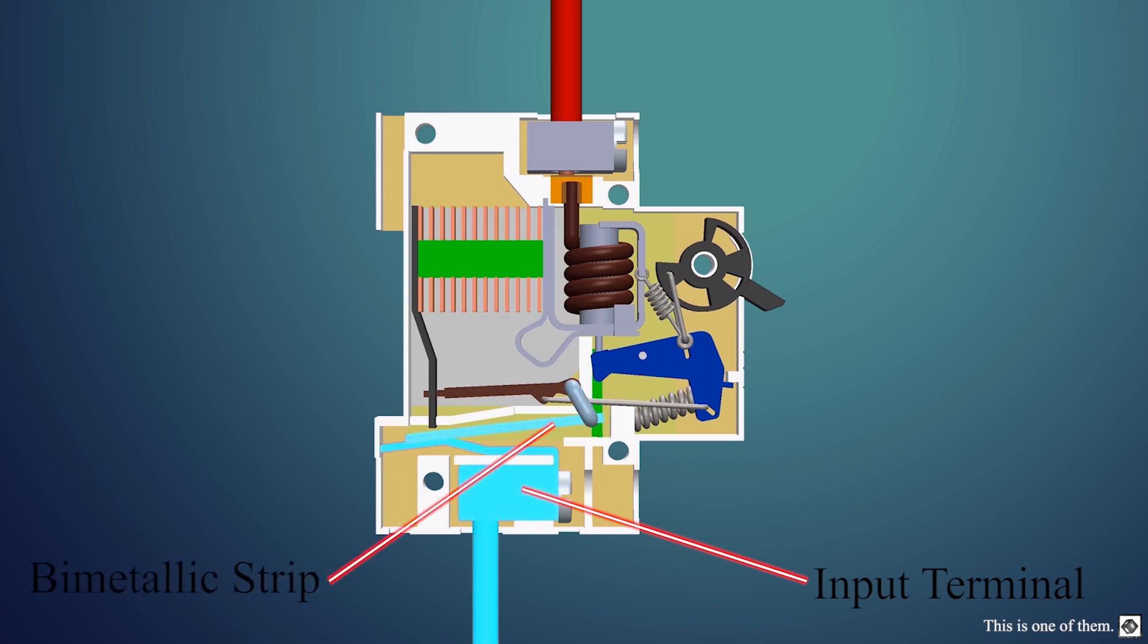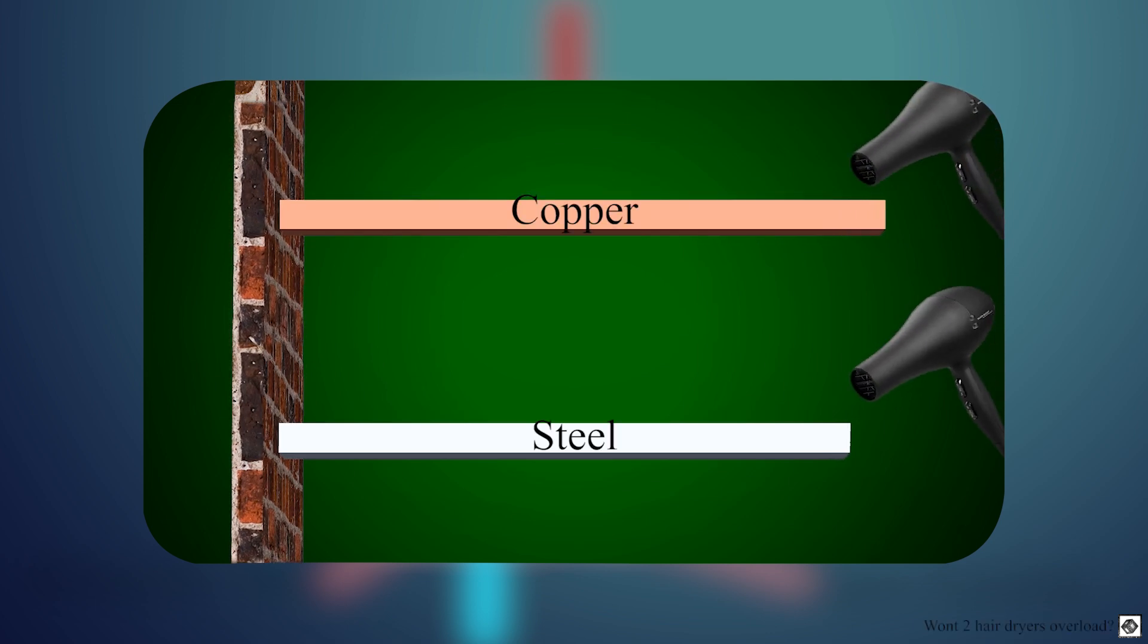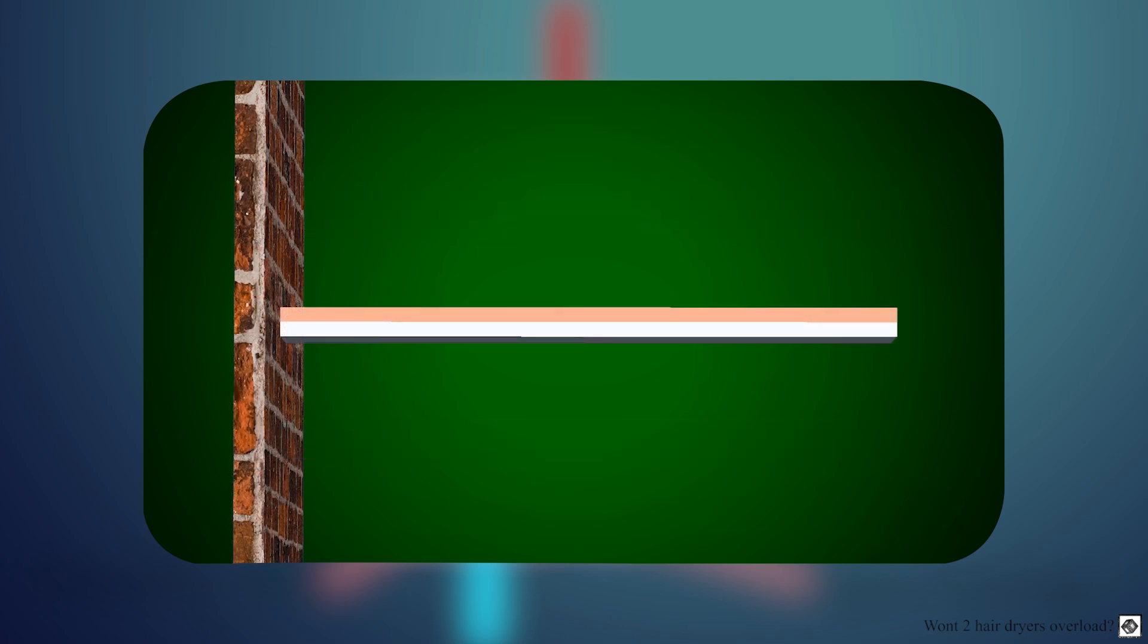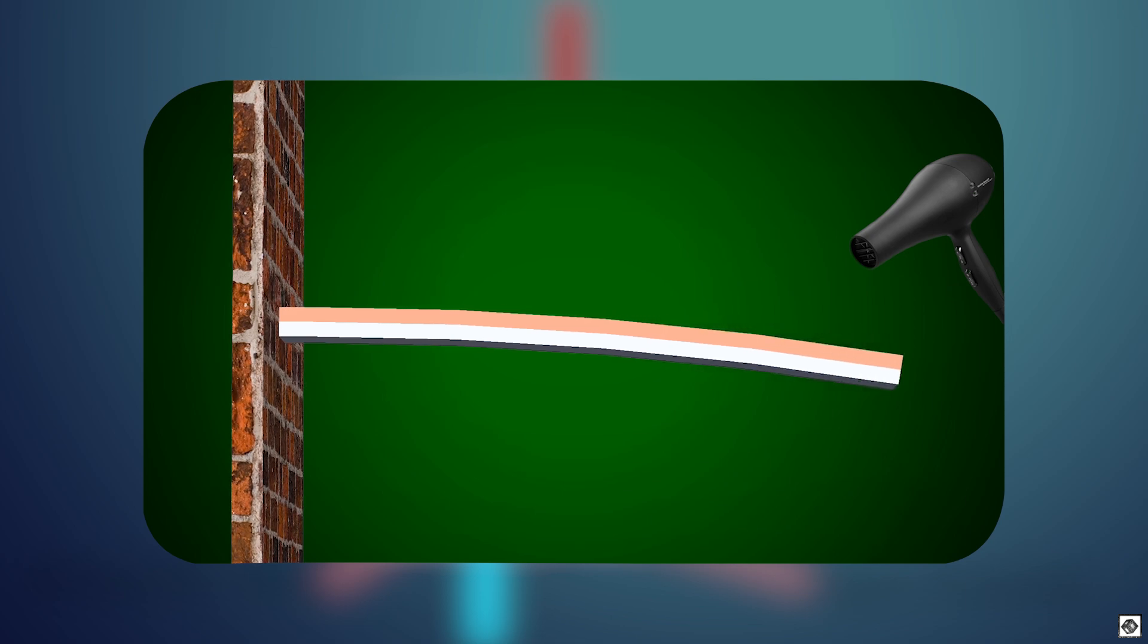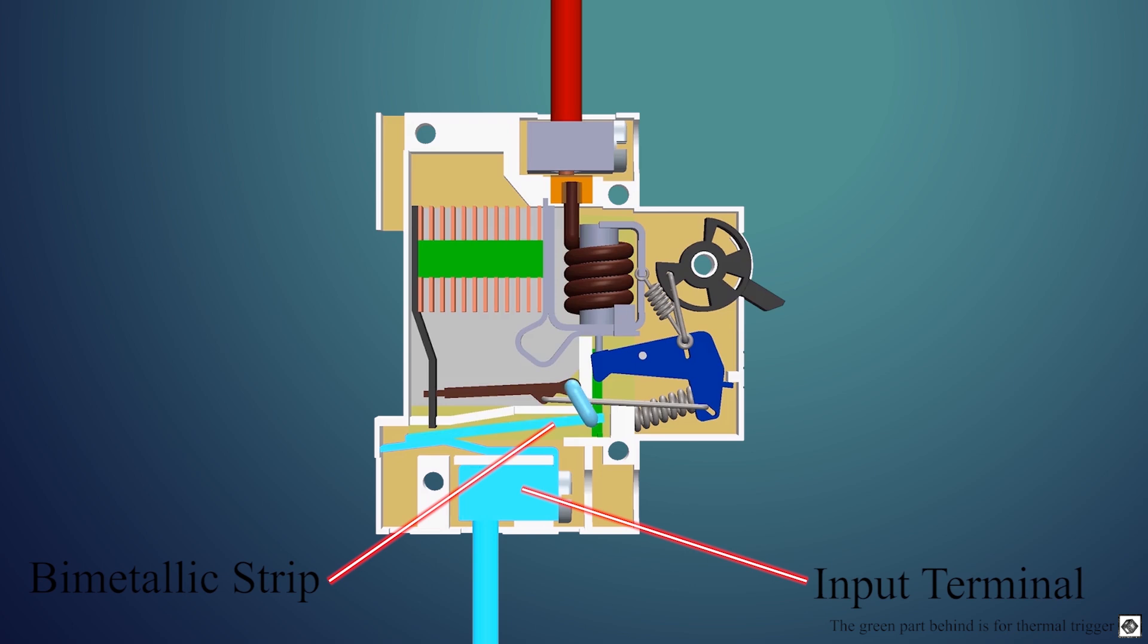Then we have a bimetallic strip. This strip is made of two different metals. When metals are heated, they expand, and different metals expand at different rates. So when we heat two different metals that are joined, they bend because one metal wants to expand more than the other. The heat to expand and bend can be generated by flowing a current, as is the case in an MCB.